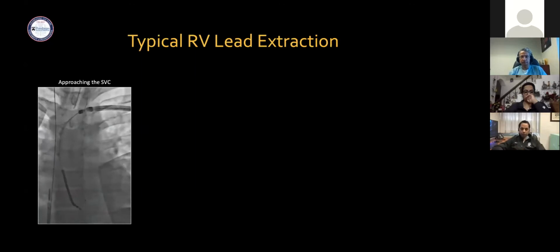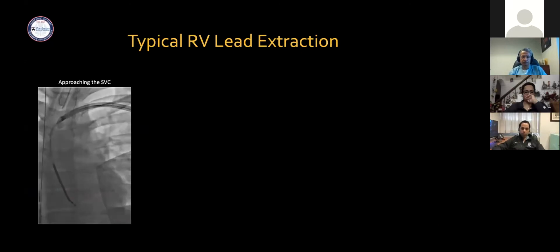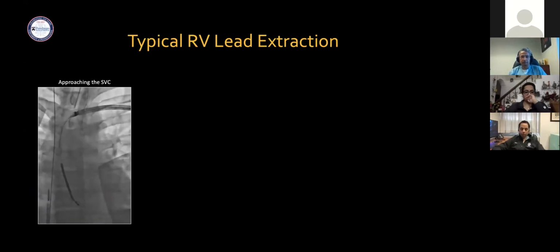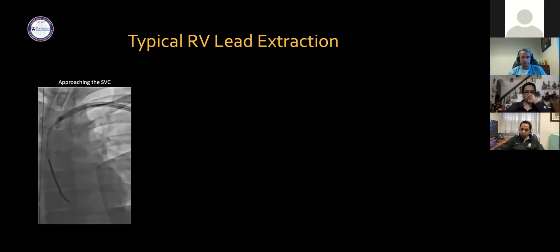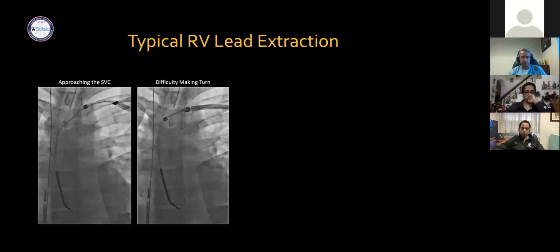But a technical lead extraction talk wouldn't be complete without discussing the use of an outer sheath. Regardless of the powered sheath that we utilize, I think it's incredibly important to utilize an outer sheath, and I'll show you why. Here we're approaching the SVC with our laser sheath, and we're having difficulty making the turn. You can see that I'm pulling quite hard on the lead. The harder you pull, the more you increase the risk of an avulsion injury. Here, a lot of people would start to lase on this lead to try to get through, but I think it's generally unsafe to lase in the SVC.